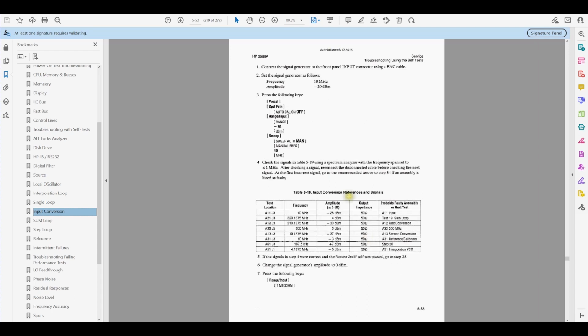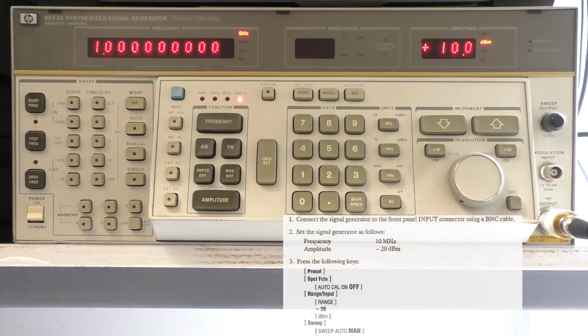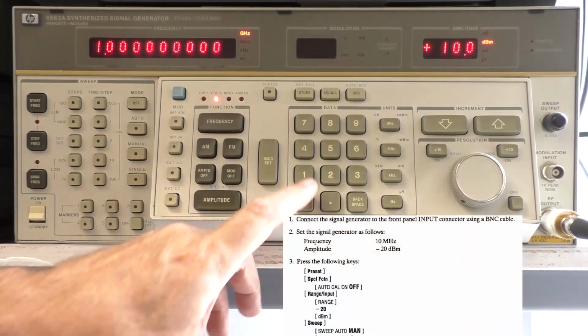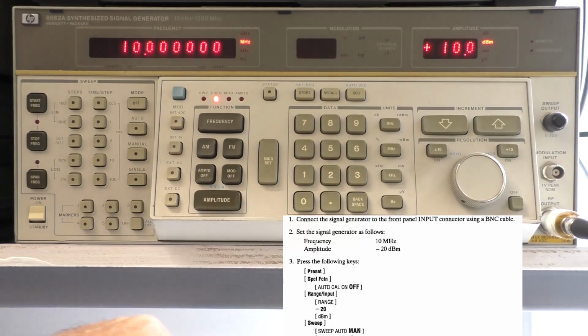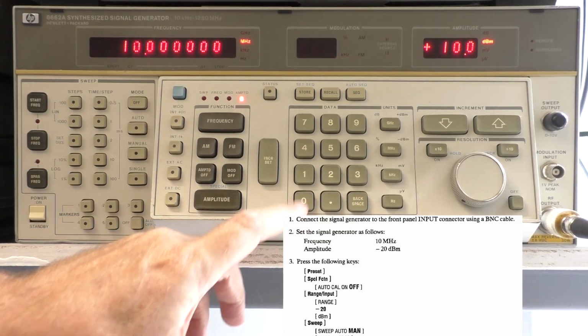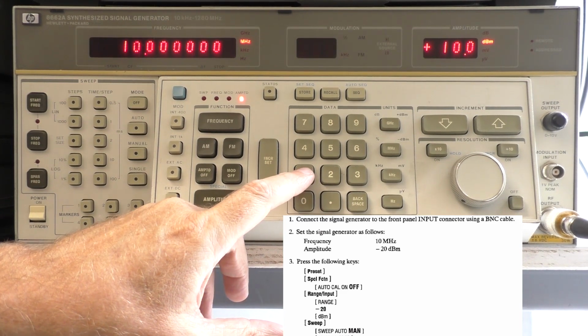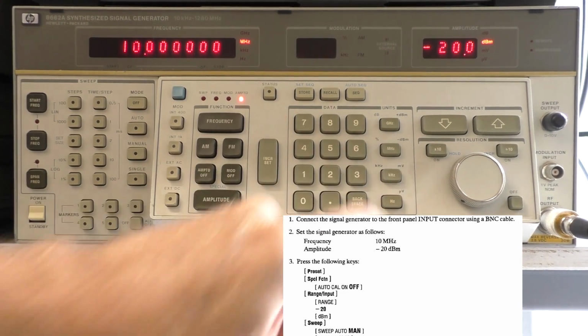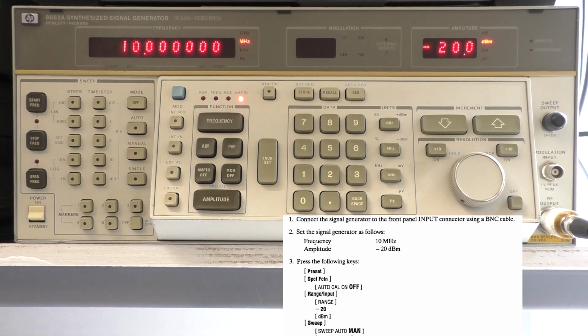We note the input conversion block diagram. Input A11 is routed to first conversion A12 and then to second conversion A13. Let's perform this test. We will make do with an oscilloscope for measurement within the signal path. Start your signal generator, let it warm up. Set the frequency to 10 MHz. Set the amplitude to -20 dBm. Plug your generator into the analyzer's input.